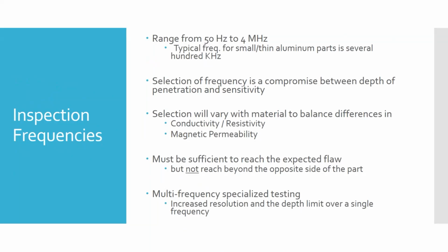It's not so much that I'm going to design the specific test, but if I'm moving from one material to another, it's a does-it-make-sense check, right? I'm setting up my probe. I used it on this before. I know that aluminum's this, and now I'm doing something else. You can use that to figure out, is my procedure correct? Is it in the ballpark? Okay.